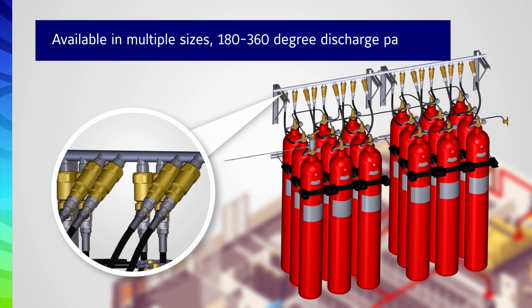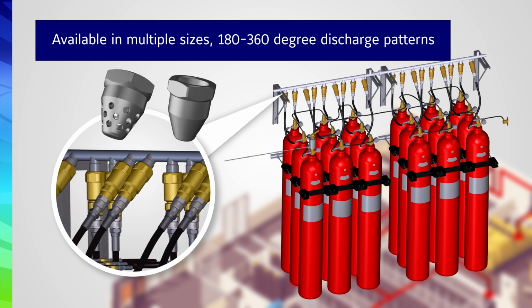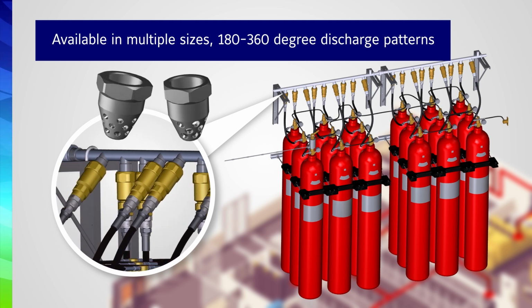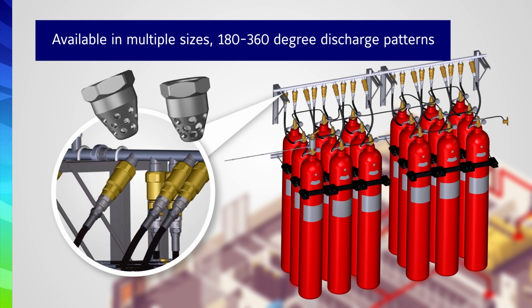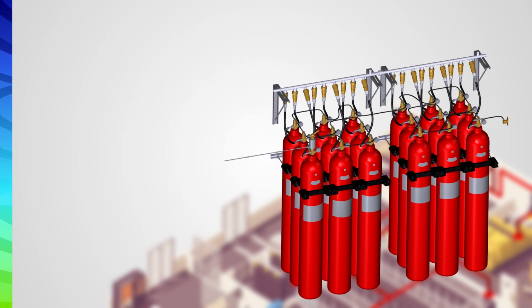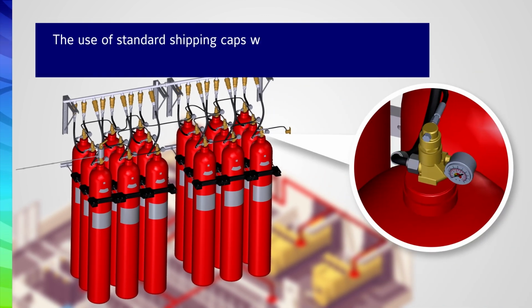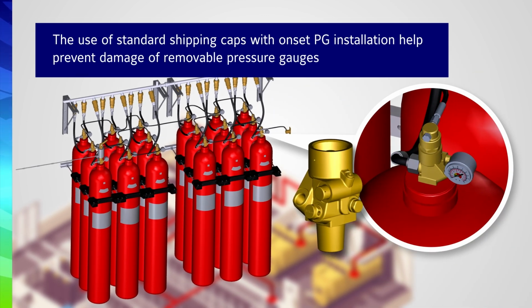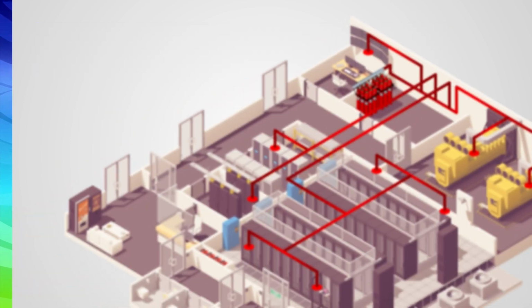Pipes use union connectors for a gas-tight seal, and discharge nozzles are available in multiple sizes and 180 and 360-degree discharge patterns. Because the HYGOOD IGS 300 uses removable pressure gauges, a standard shipping cap can be used on each container, helping prevent damage during transportation. The separately supplied pressure gauges are easily installed on site.